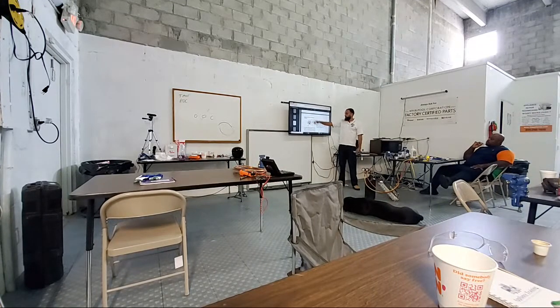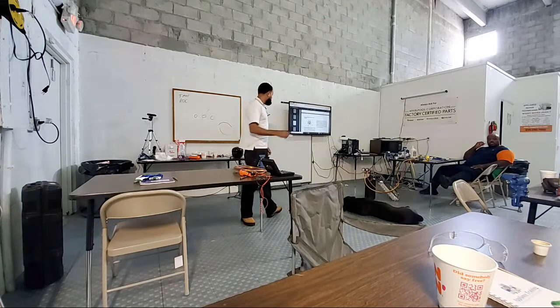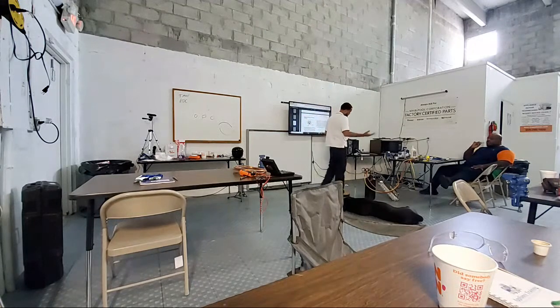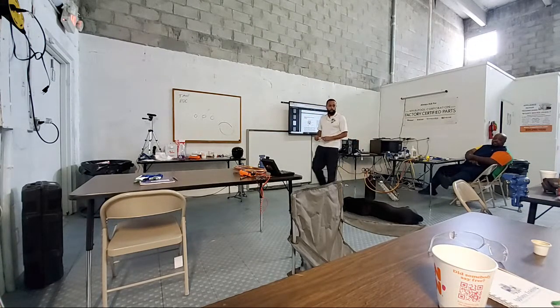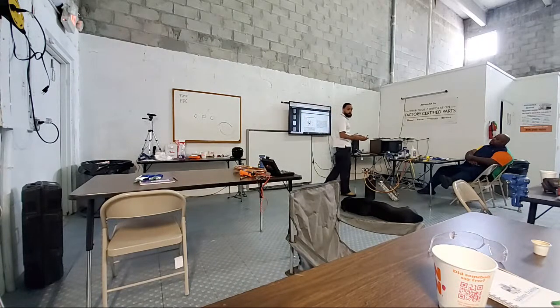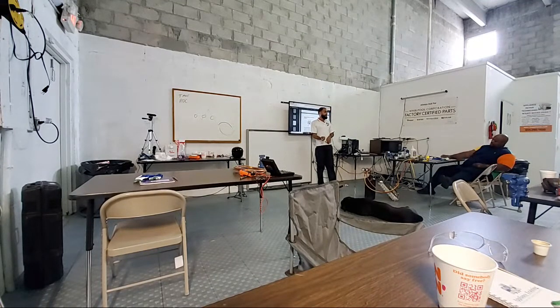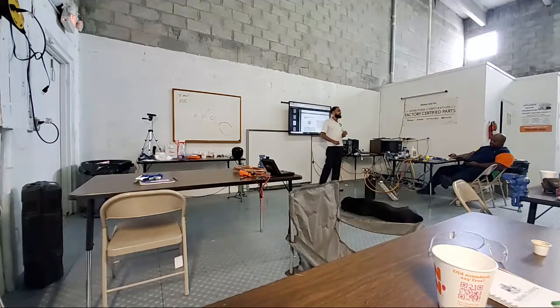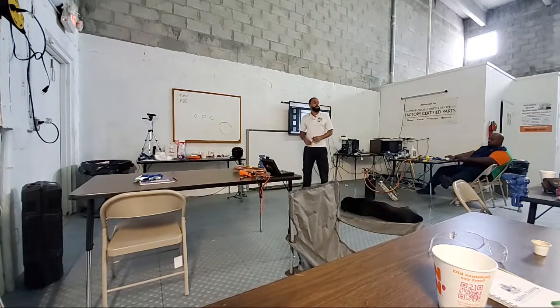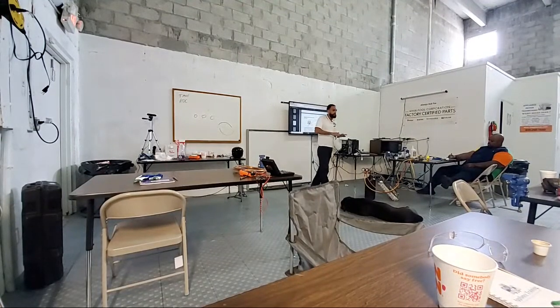Here's your wires. So how will we check a defrost thermostat? Well, what kind of test can we do? Ice test. What does that mean, ice test? Put it in water? Yep. A cup of water. But this isn't even easy. Go on Amazon and buy yourself a can of keyboard cleaner. You know keyboard cleaner? Turn it upside down. Make sure you don't spray it on your fingers, and spray it at it. It will frost up and will definitely speed things up, because sometimes the water doesn't work. Yeah, keyboard cleaner. You'll actually hear the disc close, and your voltmeter will give you continuity.